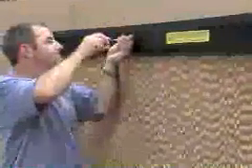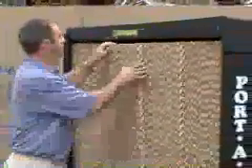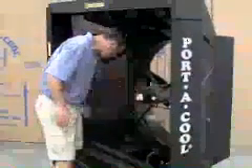To check or replace the pads, simply remove the far right and center screw on the pad flap and swing the flap down to the left side of the unit. The pads will easily lift out of the unit. For ease of removal, start with the center pad. Once you've removed the pads, make sure the sump pump is clean and free of debris and dirt.